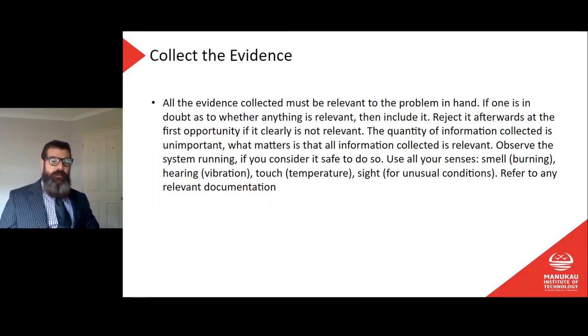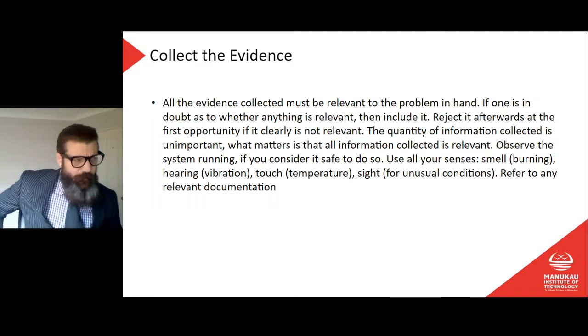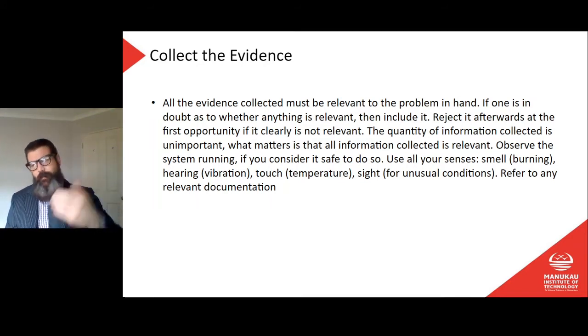Use all your senses: smell, hearing, touch, sight. Refer to any relevant documentation. And now, in terms of assessing whether things are relevant, here's something I would add, again from my own personal experience, which I don't think is covered here: look for the common factor, or go to the common factor first.